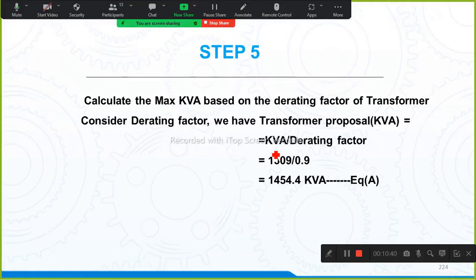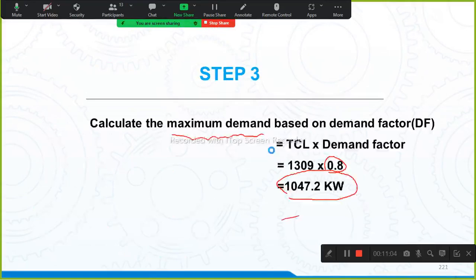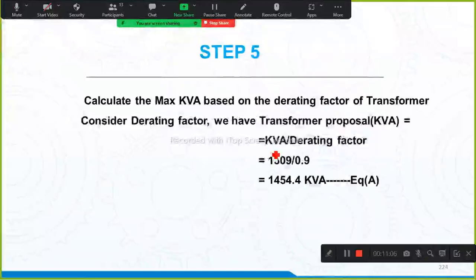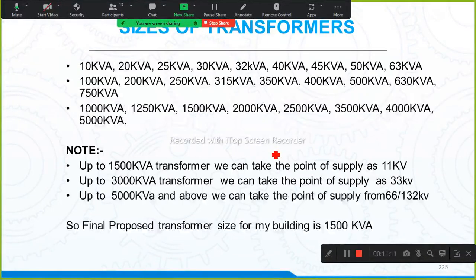So now step 5, calculate the maximum KVA based upon the derating factor of the transformer. Considering the derating factor, KVA is equal to KVA divided by the derating factor of the transformer. So what is the KVA value? 1309 KVA is the total KVA divided by the derating factor of the transformer, 90%, that is 0.9. When I calculated, the transformer size we got is 1454.4 kVA. So total building load को power देना है तो मुझे कितने से इसका ट्रांसफॉर्मर चाहिए? 1454.4 kVA transformer required. But is 1454.4 available?